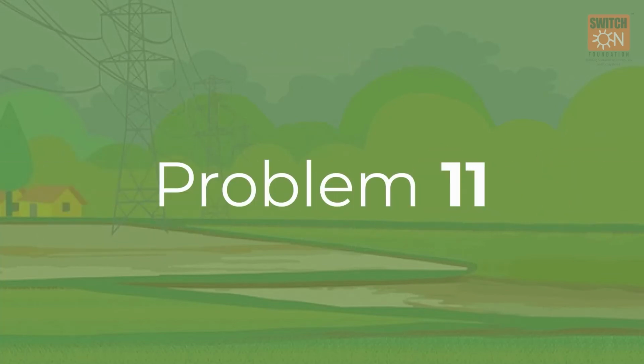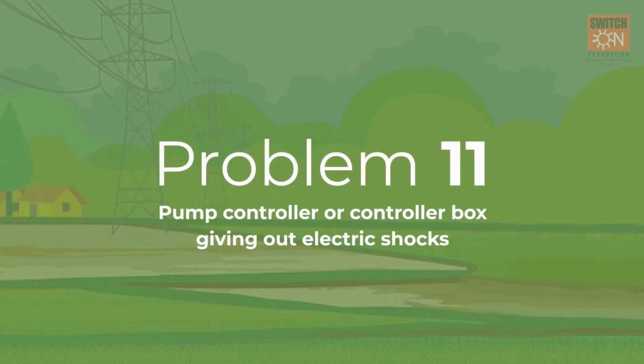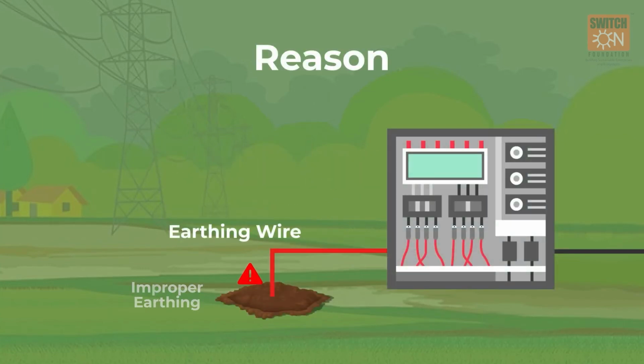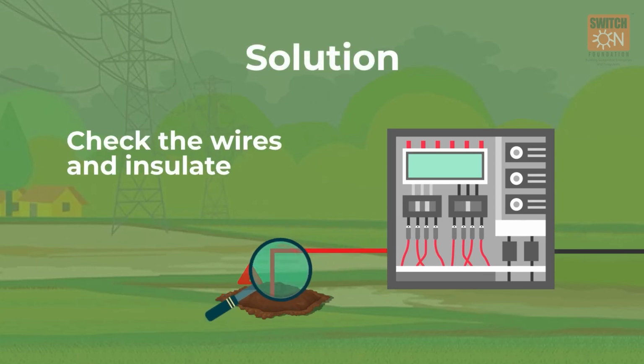Problem 11. Pump controller or controller box giving out electric shocks. Reason: improper earthing or earthing connection. Solution: first, check the wires and insulate them properly, ensuring no naked wire is touching the controller box.